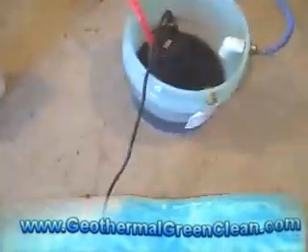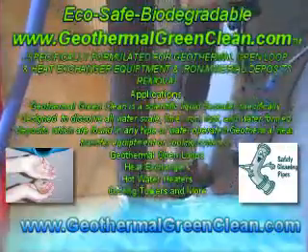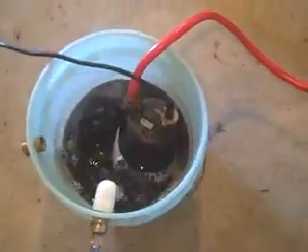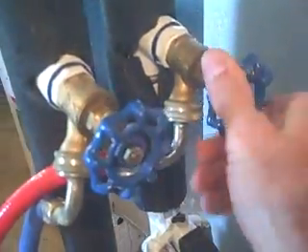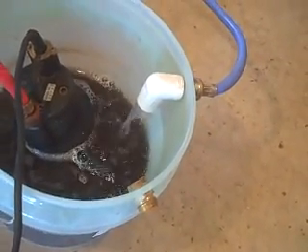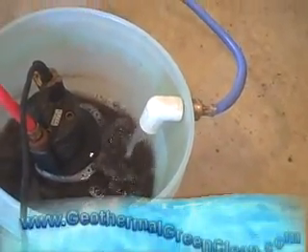We poured two and a half gallons of Geothermal Green Clean into the bucket. All you do is plug it in and the pump kicks on. We're going to open the bypass valve, open up both of these valves, and start pumping. We opened up the valve on the flow controllers and both of the boiler drains. You don't need to run this back through very fast — as you can see, it's going in pretty slow, and that's exactly what we want.